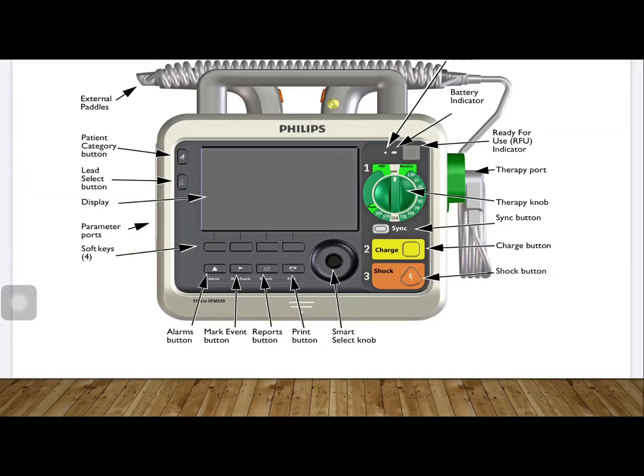So this is the front side of our defibrillator. We have here the battery indicator. It indicates if it is fully charged or low battery. For our RFU or ready for use indicator, the good thing about our defibrillator is that we have an RFU or self-test. The machine itself will run a test on its own for hourly, daily, and weekly self-test. So you can really guarantee that our defibrillator is always ready in case of emergency.